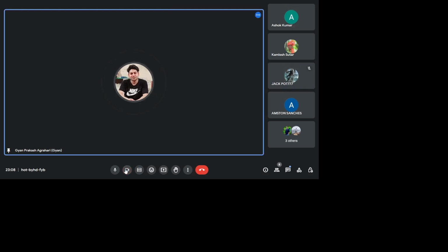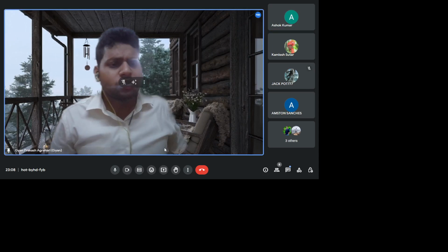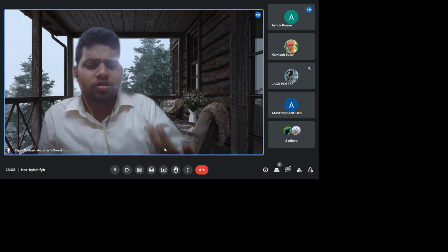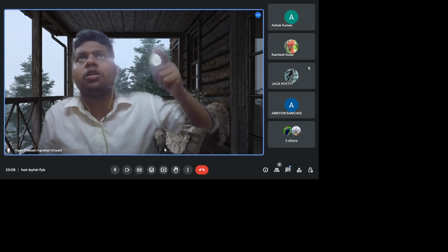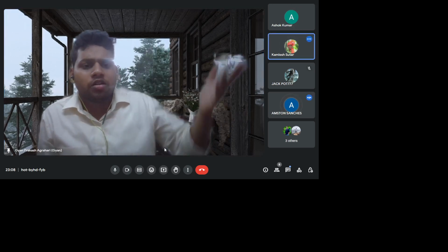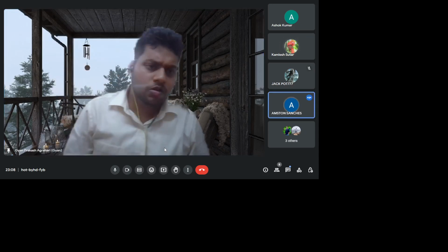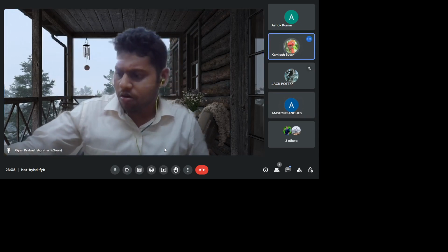The question is how water movement happens between the steam drum and the water drum. I'll try to answer. There are two methods: forced circulation and natural circulation.